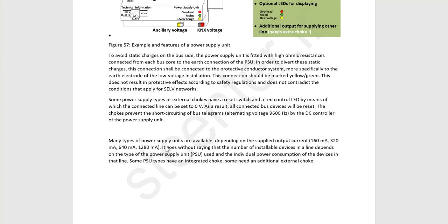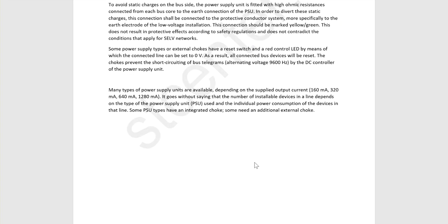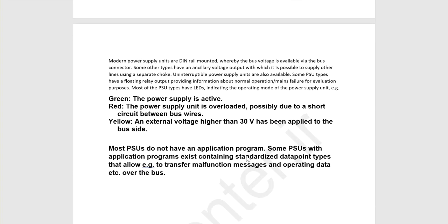As the book said, many types of power supply units from 160 milliamp to 1280 milliamp exist in the market. And there is no information on how many devices you can connect to this power supply. Always you should make the calculation and see what the power consumption of the devices is. Modern power supply units are DIN rail mounted, whereby the bus voltage is available via the bus connector. Some other types have an ancillary voltage output with which it is possible to supply other lines. I said this about the yellow and white.